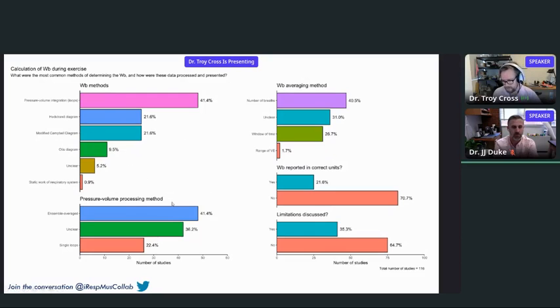When we make these measurements, though, before you actually get your joules or joules per minute for power measurements, you've got to process this pressure volume data, and that's another critical thing for someone learning the field. You can take many breaths and average those breaths together to get a representative ensemble averaged loop. Or you can calculate the work of breathing breath by breath, and then average those individual values. Might not sound like much to you which way to do it. And in reality, we don't know which way is better.